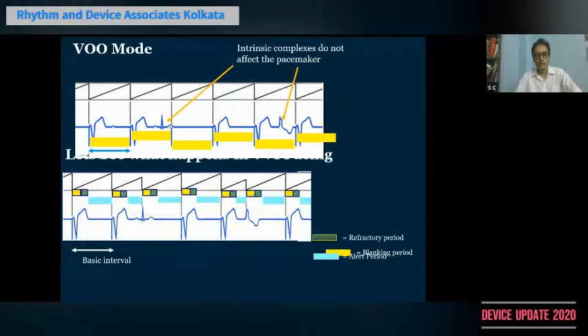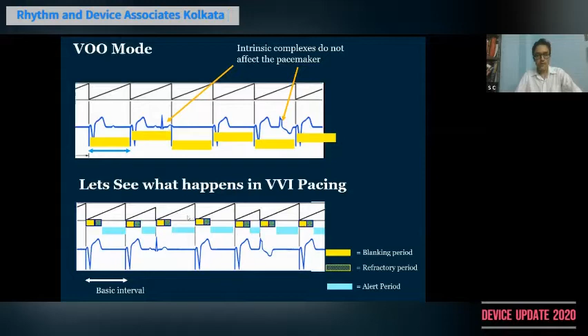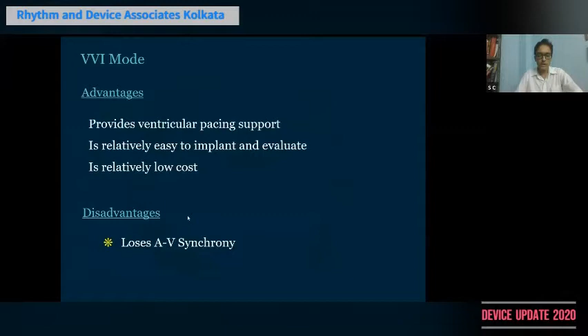So in VVI pacing, what will happen is that intrinsic QRSs will be detected, and you won't have R on T or arrhythmic events going on. The advantage of VVI mode is that it provides ventricular pacing support, is relatively easy to implant and evaluate, and the main advantage in our settings is relatively low cost. But this comes at the cost of loss of atrioventricular synchrony. You are not sensing whatever is going on in the atrium, and you can't track the atrial waves. So there is loss of atrial synchrony. The atrium is contracting in its own fashion, and the ventricle is contracting according to whatever base rate you have set.